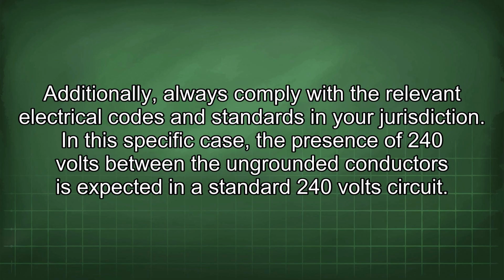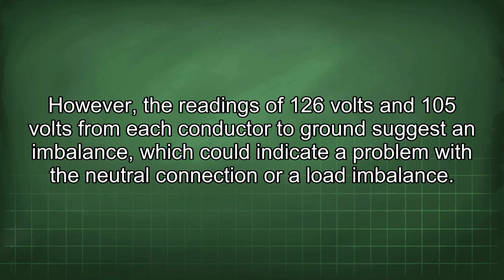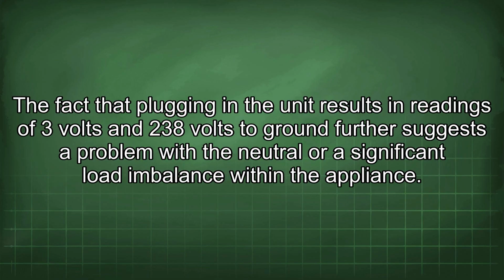In this specific case, the presence of 240 volts between the ungrounded conductors is expected in a standard 240 volt circuit. However, the readings of 126 volts and 105 volts from each conductor to ground suggest an imbalance, which could indicate a problem with the neutral connection or a load imbalance. The fact that plugging in the unit results in readings of 3 volts and 238 volts to ground further suggests a problem with the neutral or significant load imbalance within the appliance.